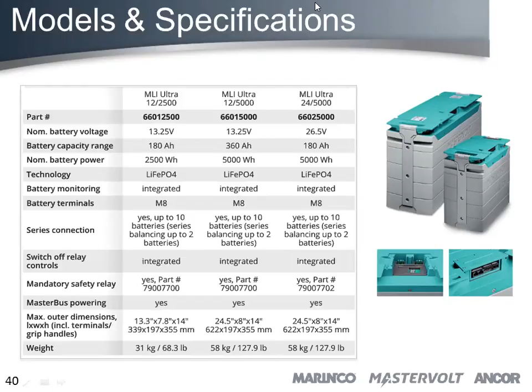Now the issue with lithium cells is that if you charge them while they're all sitting in series, one battery could take more capacity than the others. Lead acid batteries do the same thing, but that automatically balances out as you charge and discharge them. With lithium batteries, you don't have that behavior - one cell could end up at, say, 100%, while another is at 95%. The next time you recharge, it will do the same thing again. Now the BMS system balances the power between the cells.